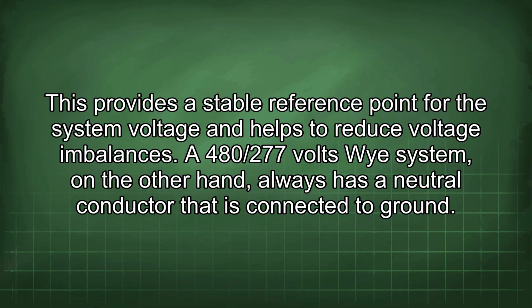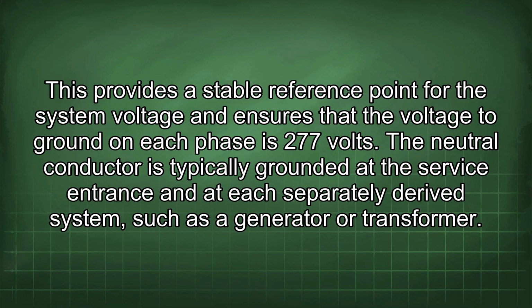A 480/277 volts Y system, on the other hand, always has a neutral conductor that is connected to ground. This provides a stable reference point for the system voltage and ensures that the voltage to ground on each phase is 277 volts. The neutral conductor is typically grounded at the service entrance and at each separately derived system, such as a generator or transformer.